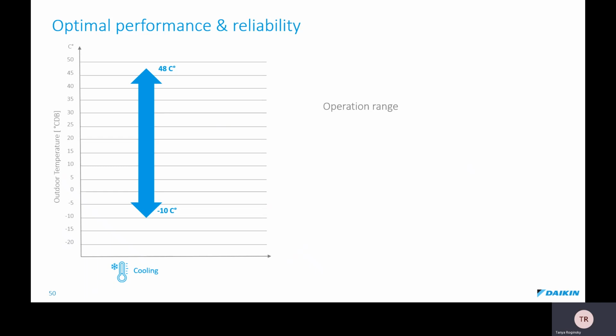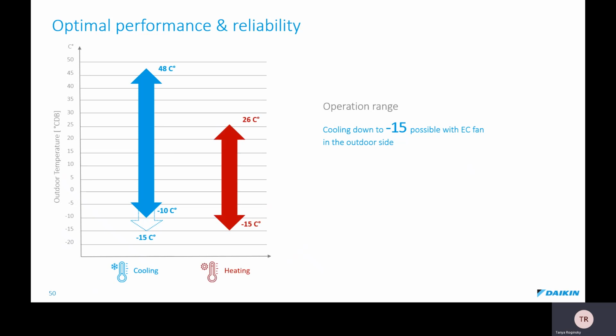Operation range. In cooling, we can go from -10 up to 48 degrees dry bulb. And we can further expand down to -15 if we use EC fans on the outdoor side. That would be a good option for technical cooling operation. In heating mode, we can operate from -15 to 26 degrees. And actually, we can guarantee the performance down to -20. We can meet different temperature requirements for a wide range of diverse climates.